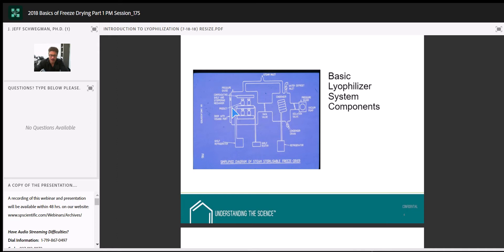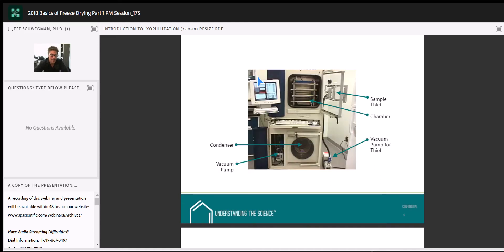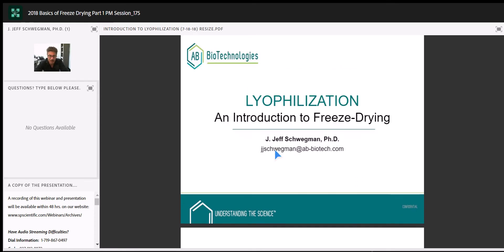This is an image of one of the development units in our lab. Same basic components: vacuum pump, condenser coil chamber, sample chamber with temperature-controlled shelves. Behind it is a tube connecting the sample chamber to the condenser coil. One thing that sets this unit apart is our sample thief — during development we pull samples at various time points to monitor potency, purity, and residual moisture, and we can do that without stopping the cycle.